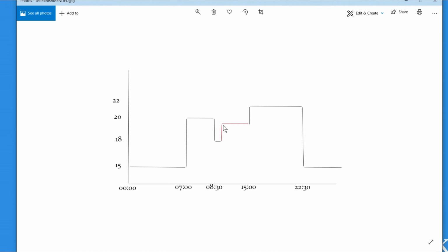What I mean is that the new set point will now be regulated at this new red line, around 20-odd degrees. And it will carry on doing that until either I put it back down again, or the next set point is reached. In our case, at 3 p.m. the new set point is reached, and then the old program takes over. So when you do override it, it doesn't override it forever. It only overrides it until the next set point that you've created.